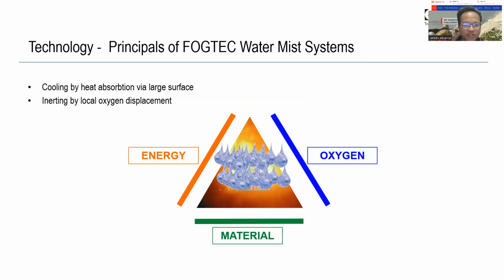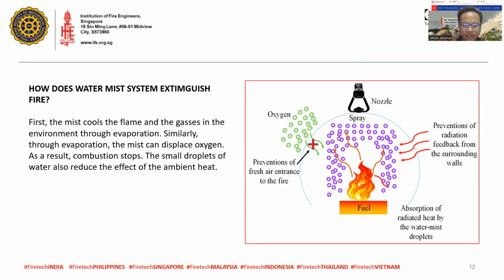Now, how does a water mist system work? From this image, you can see that a fire has energy, oxygen, and material. The water mist system suppresses fire by cooling through heat absorption via a large surface area and also by inerting through local oxygen displacement. If you look at this figure, once the spray of mist of water is discharged to the fire, first the mist cools the flame and the gases in the environment through evaporation. Similarly, through evaporation, the mist can displace oxygen. As a result, combustion stops. The small droplets of water also reduce the effects of the ambient heat.